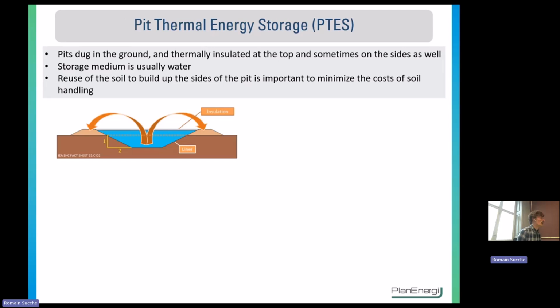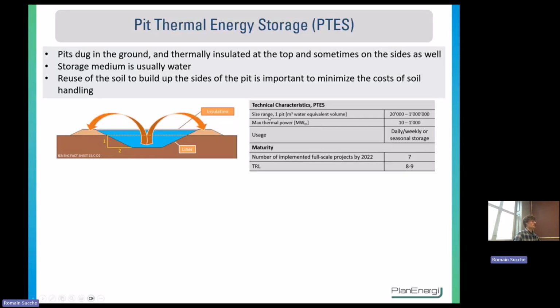The second technology is the pit thermal energy storage, which is essentially a pit that is dug in the ground and which is insulated, always at the top, sometimes also at the sides. And basically, the idea is to dig soil and put it on the side, so as to minimize the cost of the storage. Otherwise, the way you can operate will be the same as a TTES with diffusers. The size of the PTES can be quite big, from 20,000 to 1 million cubic meters of water, with the same kind of thermal power input and output.